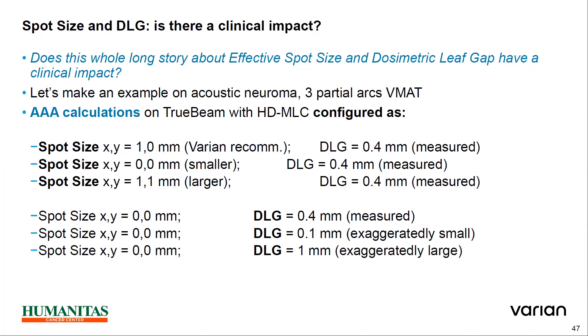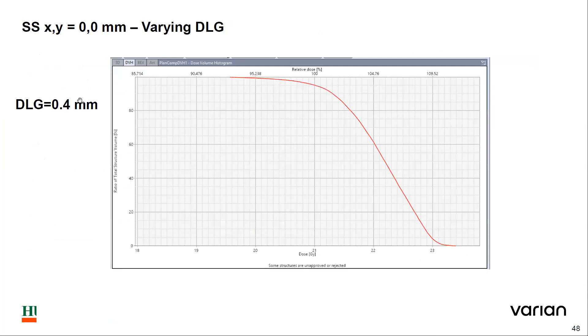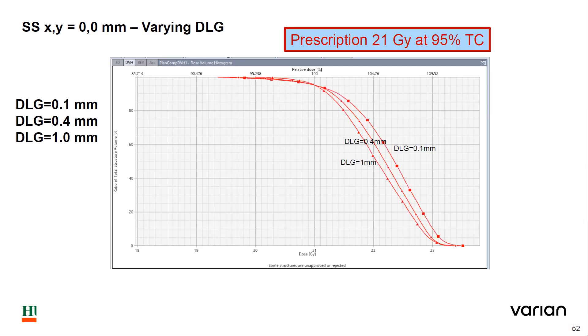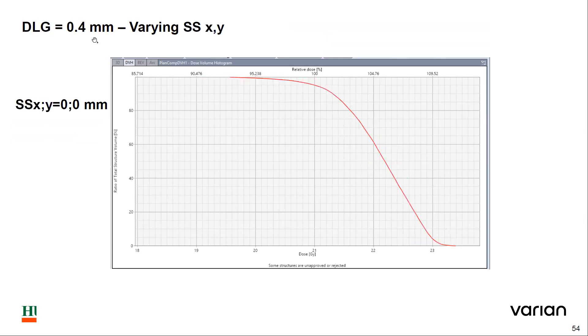What is the clinical impact? Does this whole discussion about effective spot size and dosimetric leaf gap have a clinical impact? Let's make an example: an acoustic neuroma, three partial arcs with TrueBeam and HD-MLC configured. DLG is varied for the MLC while spot size is fixed. The mid-range DLG is 0.4 mm, with values of 1 mm and 0.1 mm tested. We can see how the dose distribution is affected by varying DLG and spot size.